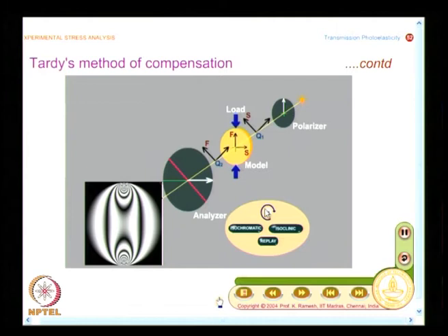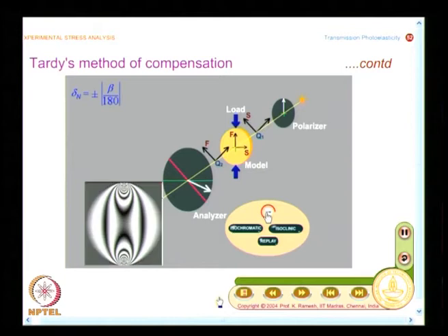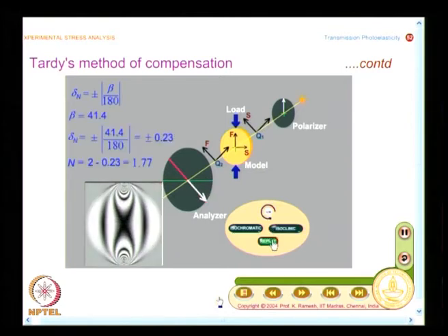So, that is why I identified it, because when you rotate the optical elements, you have to visually check whether you have reached the minimum intensity. So, one check is it forms a figure of 8; even if you rotate the element slightly this way or that way, the figure of 8 will get disturbed. That is one indirect check. So, what we will do is rotate it in a clockwise direction. I rotate it in a clockwise direction, what happens? You may not have noted all aspects, it has formed the figure of 8.